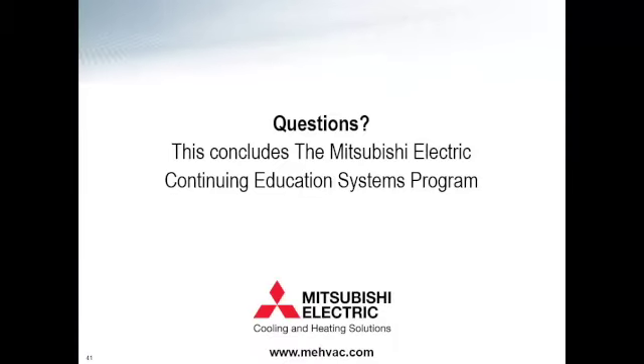You mean heat recovery on your heat pump system? So if you're going to be providing heating and cooling to the space, introducing that BC controller will allow you to 100% shut off. If you have no BC controller, the indoor unit needs to leave its linear expansion valve about 2% open, just so that refrigerant can always be cycling through the system. With the BC controller, we have the diverting valves, so you don't have to deal with that. You can close off any given indoor unit to 0%. Otherwise there's hot or cold refrigerant bleeding through, even 2% of it, through an indoor unit, which can affect the load in a really tight passive house space.